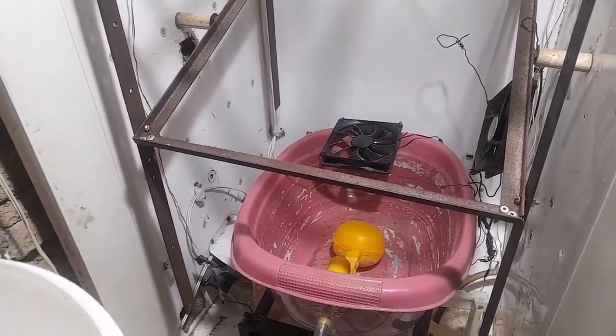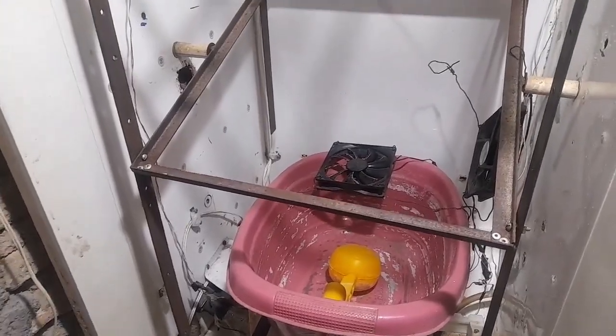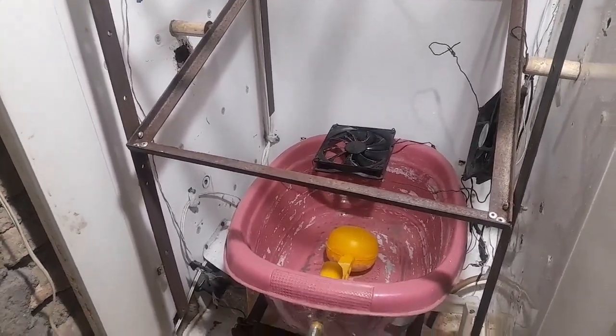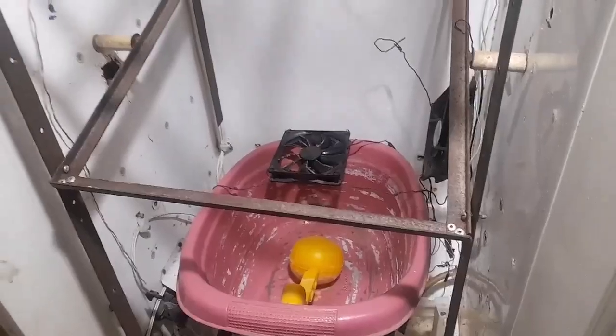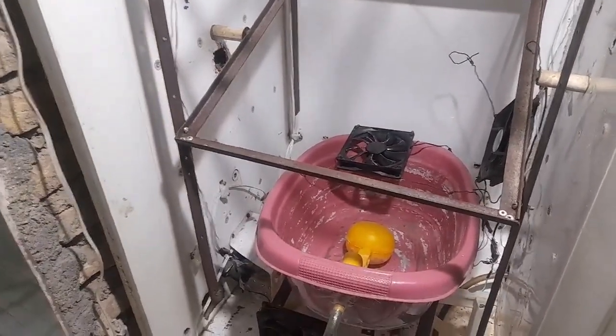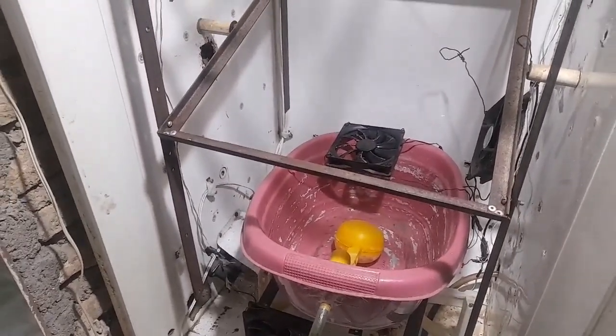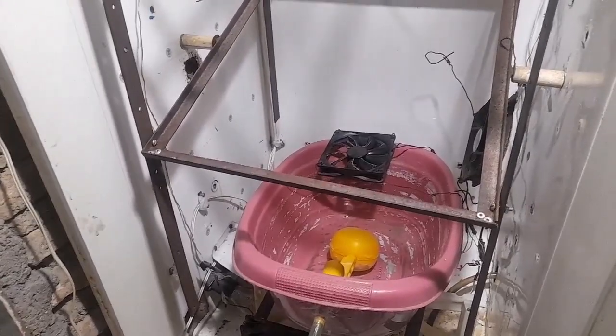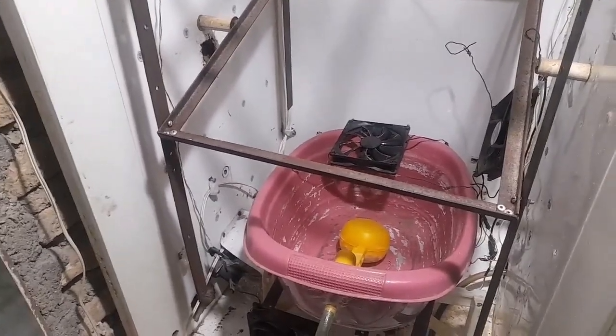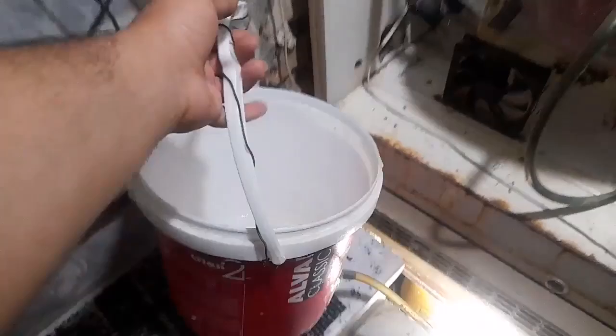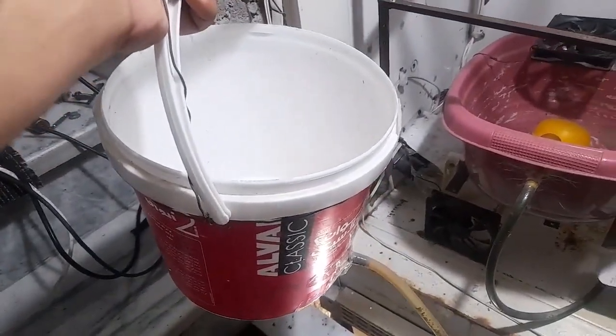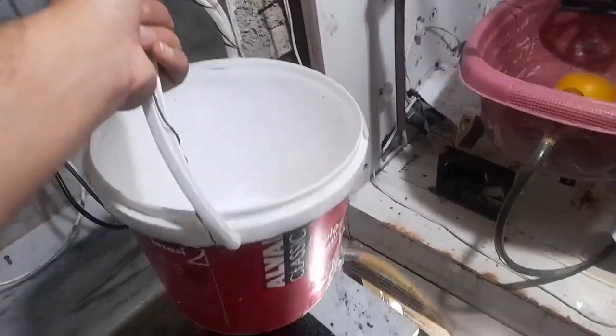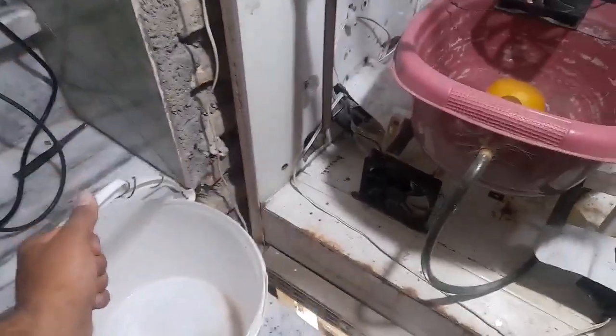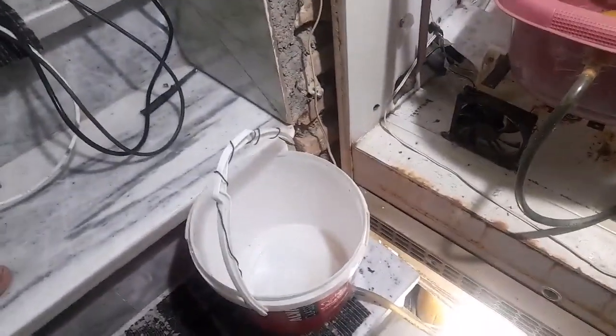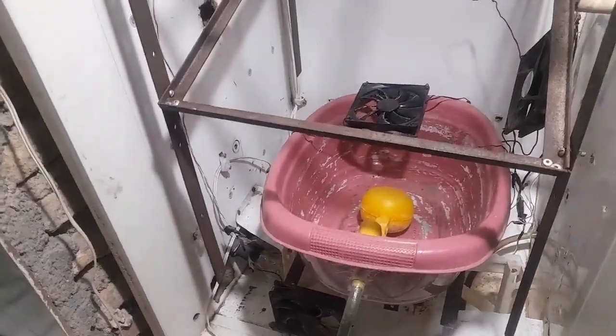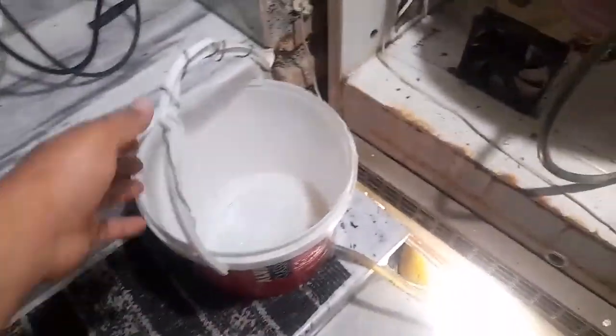Personally, I recommend using a 10 or 20-liter water container instead of connecting it directly to your home's water supply. Why? Because if the float valve ever fails while it's connected directly to the plumbing, water could continue flowing into the incubator without stopping. That could flood the entire system. Using a separate water container limits the maximum amount of water available and makes the system much safer. A 10-liter container is usually more than enough and may only need to be refilled once every several days, depending on your incubator's operating conditions.